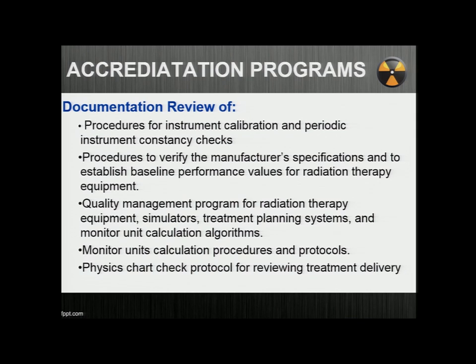So procedure, what does it look like in their center? What do their procedures look like? Their guidelines or go-bys. Procedures to verify manufacturer specifications and establish a performance baseline from there, especially for radiation oncology equipment testing. I think of the CT world also and how they differ, and certainly with our manufacturers, they differ a little bit. Quality management program for radiation therapy equipment, simulators, treatment planning, just like I said before. Also, their second check monitor unit calculations. There's a lot of checks and balances in place before they beam on.